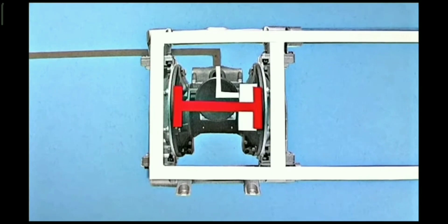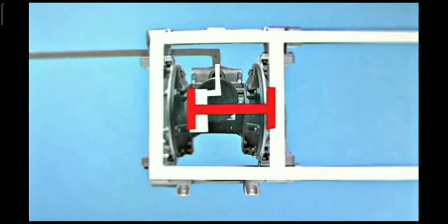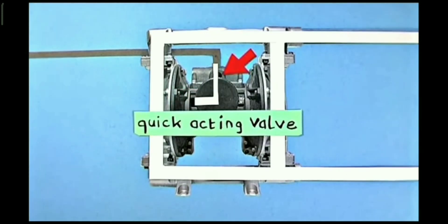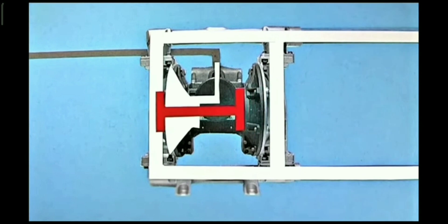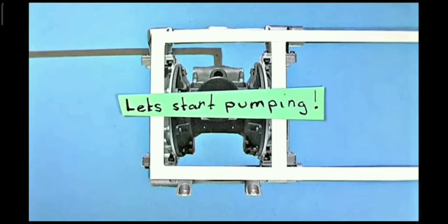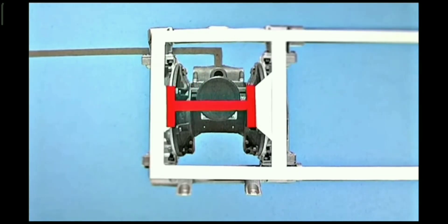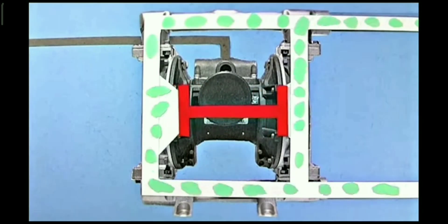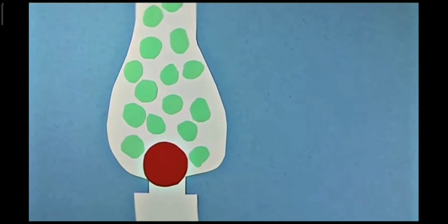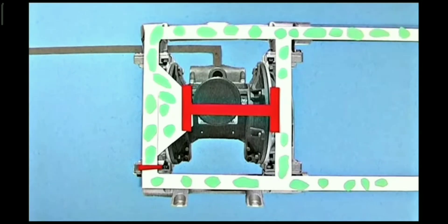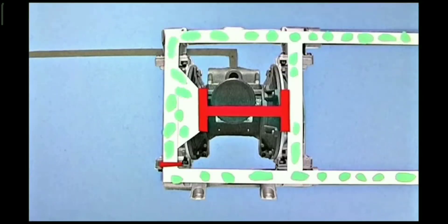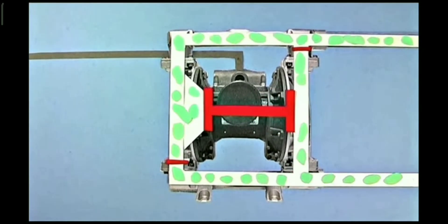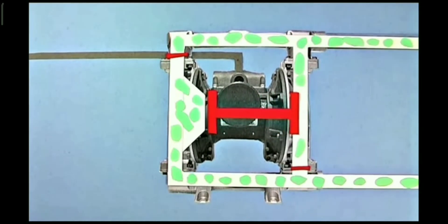The pump's operation relies on the movement of a flexible diaphragm at the middle of the pump. It releases compressed gas or air which drives the momentum of the flexible diaphragm. The diaphragm then undergoes a reciprocating back-and-forth motion. As the diaphragm moves, it creates changes in volume within the pump chamber, causing fluid to be drawn in and expelled.